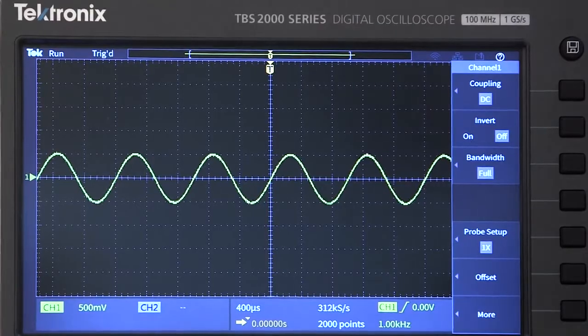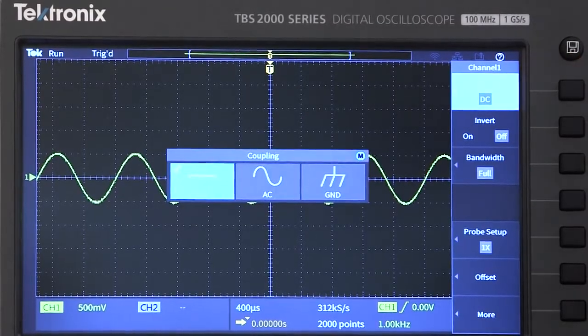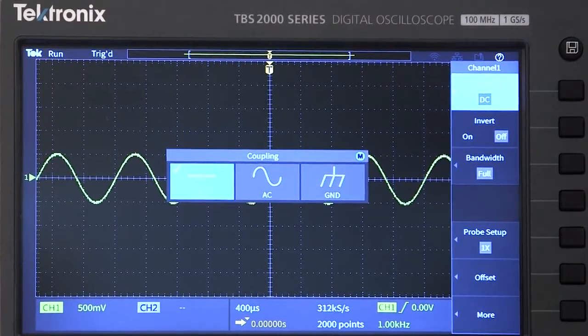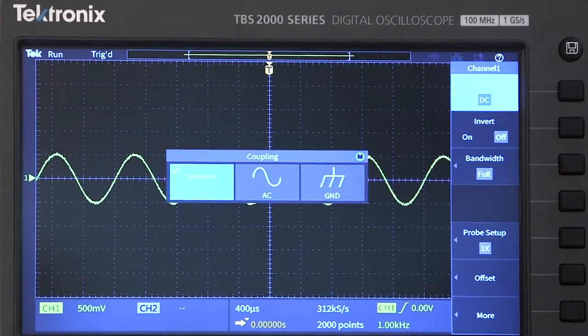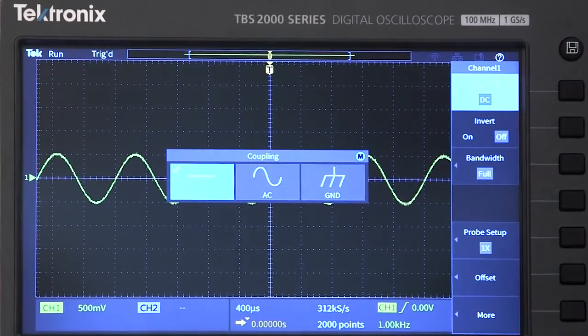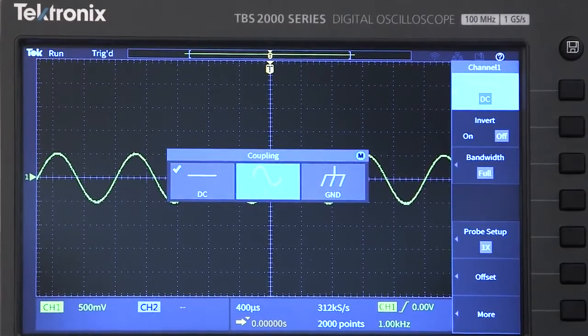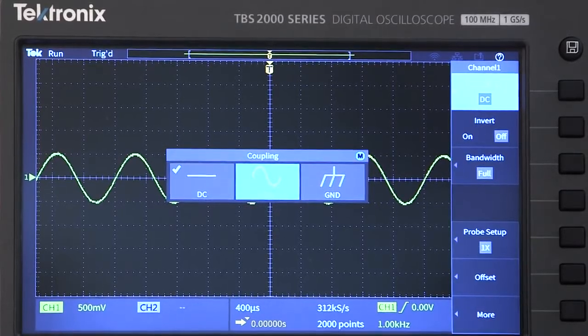Coupling is a useful vertical setting. It defines the way the signal is connected to the oscilloscope input. DC, or direct coupling, passes both AC and DC components of the signal, so you can see any DC offset if the signal has it. AC coupling blocks any DC offset in the signal and passes only the AC component. This mode is really useful when you want to look at the small fluctuations riding on a DC offset, like ripple on a DC power supply.